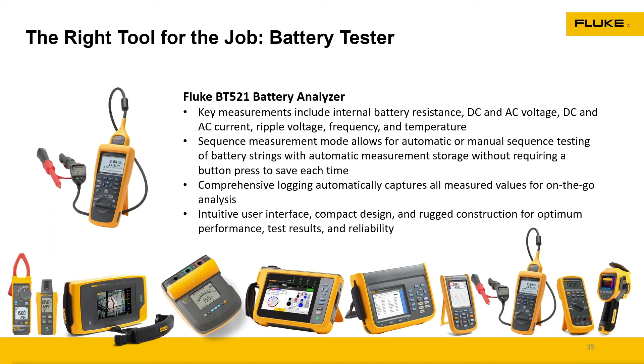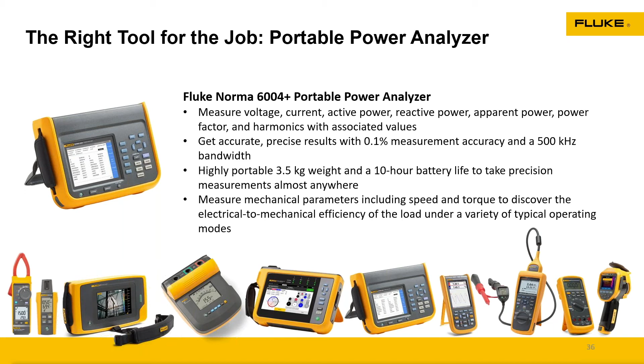The next ones are going to be important, especially on that AC side. Now, the Norma 6004 power analyzer will do DC and AC power analyzing. It's one of the first ones out there. Typical analyzers will only do AC. So this is a huge win to be able to validate what's happening on the input as well as the output. You're going to be able to do some inverter efficiency measurements with this type of meter.